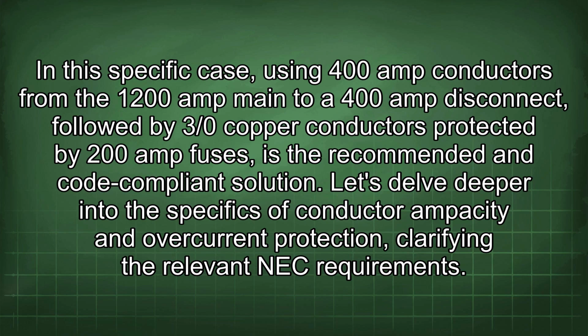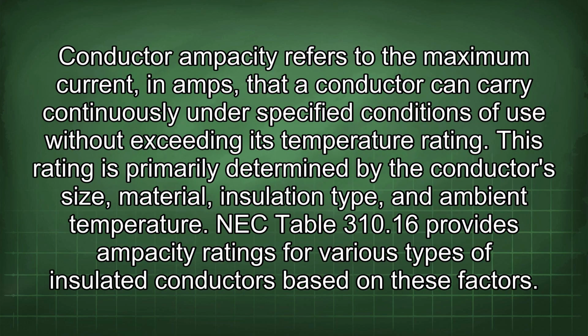Let's delve deeper into the specifics of conductor ampacity and overcurrent protection, clarifying the relevant NEC requirements. Conductor ampacity refers to the maximum current in amps that a conductor can carry continuously under specified conditions of use without exceeding its temperature rating. This rating is primarily determined by the conductor's size, material, insulation type, and ambient temperature. NEC Table 310.16 provides ampacity ratings for various types of insulated conductors based on these factors.